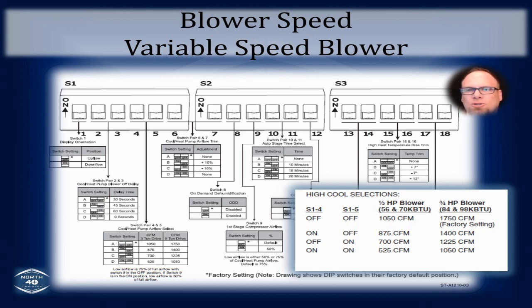But if you had the larger size furnaces, the 84,000 and 98,000 BTU furnaces, then you're going to have the three-quarter horse blower, and that same configuration of dip switches, switch bank 1, dip switches number 4 and 5, will then equal 1,750 CFM. Okay, so you have to make sure that you've got the right blower that you're looking at here as far as your terminal settings and when you set up your dip switches for an ECM motor. Now, it's not rocket science. And some people set these up and they say, well, how do I know that it's actually achieving that? Okay, well, here's a secret.